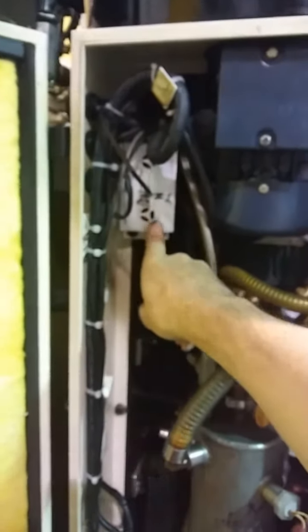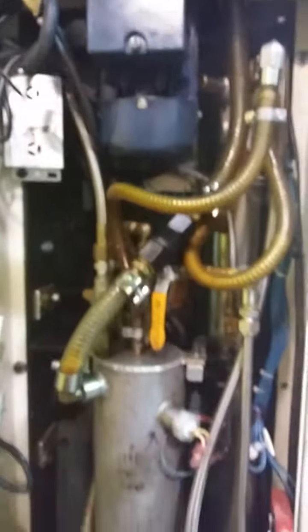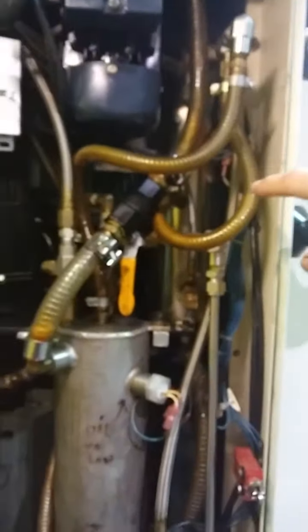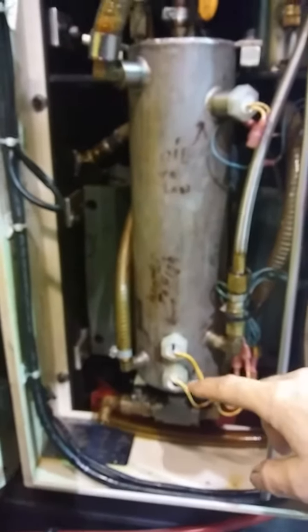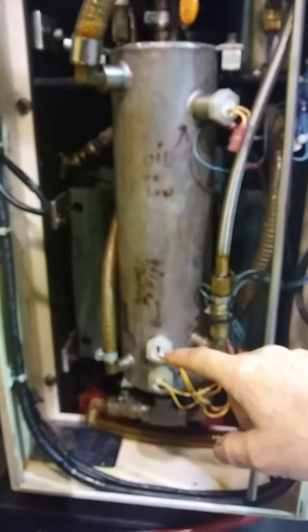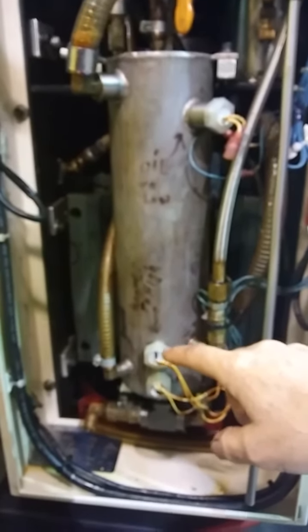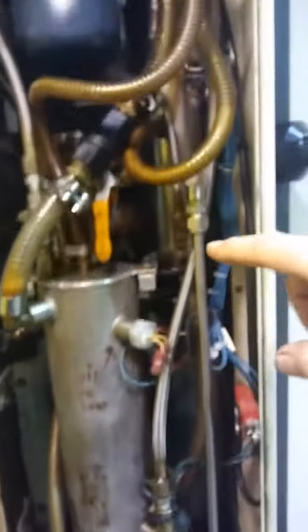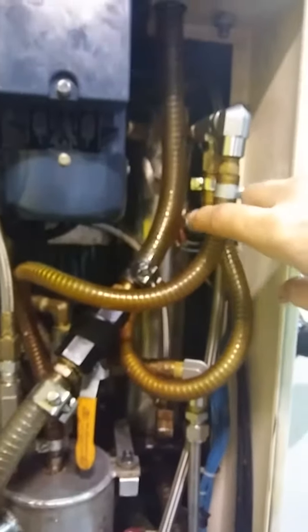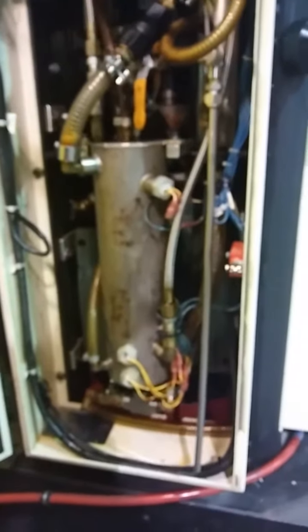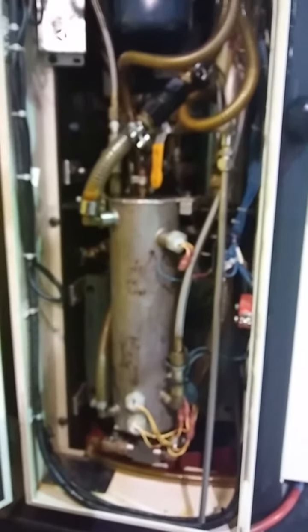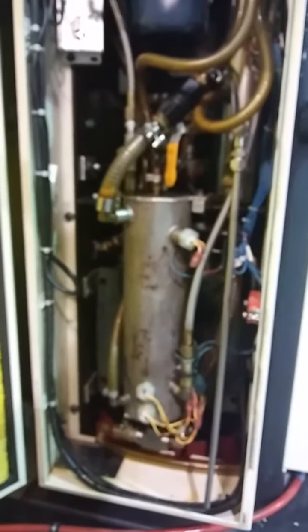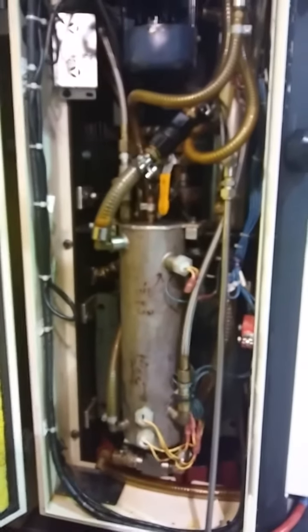These are the gas detection in different zones. This is zone 2, which is a network gas detection system. We have different vessels that store oil and non-compressibles where they end up back into the system. Different levels where we can read if there's water in the oil in a safe mode, and if it reaches this point, then it should be drained out. If the water builds above that, the level of oil and water combined can exceed a certain limit, and we look for that, and it would indicate a hard alarm, stopping the machine and notifying the user that there's an issue. He doesn't have to worry or wonder about it. Everything in the information center and the HMI tells you exactly what's going on.